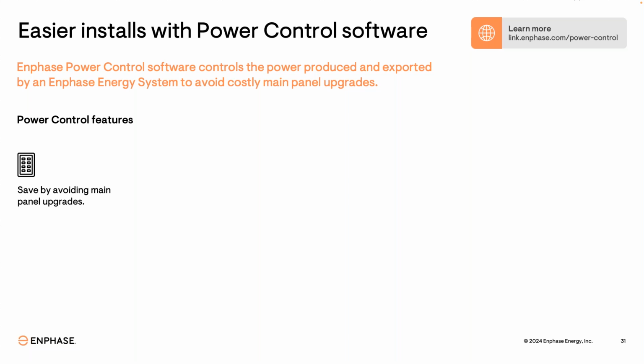For those not familiar with power control, in a nutshell, it monitors electrical current within an Enphase system and can actually control the flow of current. The purpose is to maintain electrical current levels within the electrical limits of the home or utility infrastructure. So you can install larger PV and battery systems than you otherwise would be able to, based on the limitations of the home. With PCS, you can often avoid the need for main service panel upgrades, which is especially useful for large PV systems when adding batteries or Enphase EV chargers.